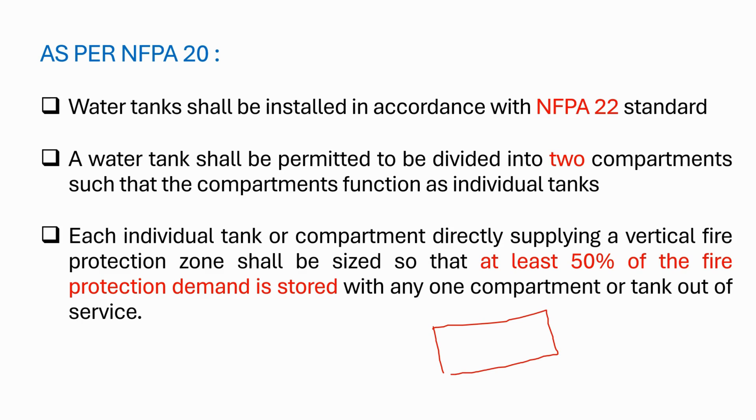For example, you have the requirement of 40,000 gallon capacity tank. This tank can be divided into two compartments or we can make it as two individual tanks. At least one tank shall have 50% of our demand. So if our demand is 40,000, then 50% of this 40,000 would be 20,000. So if it is 20,000, the other tank would also be 20,000 or other compartment is also 20,000 gallons. So whenever we are doing any maintenance, one tank can be cleaned, but the other tank shall have minimum 50% of our fire protection demand.